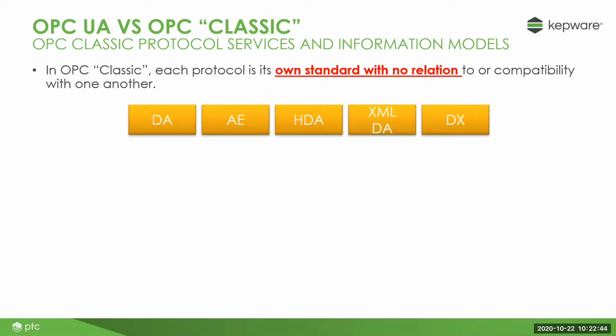Alarm and events is typically used in DCS. If you go into DCS, like the marine sector, you'll see a bunch of OPC alarm and events. But outside of that, in manufacturing, you probably won't see it, because typically the alarm and events portion is handled by the SCADA side. When you deploy your SCADA, you buy the alarm and event module and use it on the software side - the software grabs the raw data through DA and then processes the alarms in its internal platform.